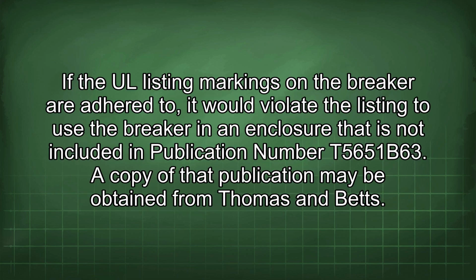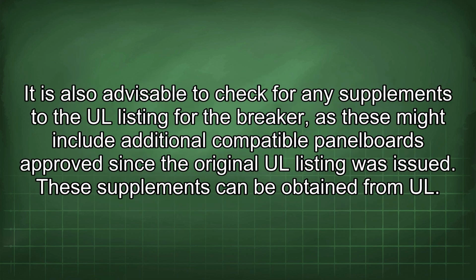If the UL listing markings on the breaker are adhered to, it would violate the listing to use the breaker in an enclosure that is not included in publication number T5651B63. A copy of that publication may be obtained from Thomas and Betts. It is also advisable to check for any supplements to the UL listing for the breaker, as these might include additional compatible panel boards approved since the original UL listing was issued. These supplements can be obtained from UL.